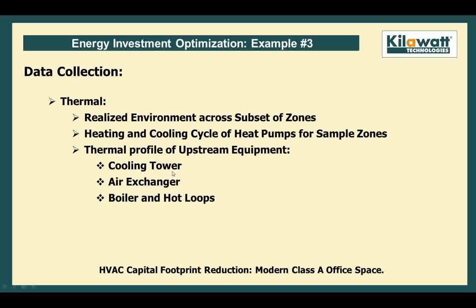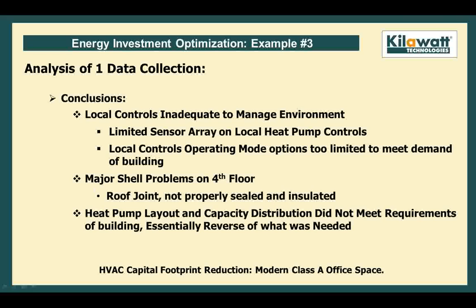The conclusions of our first level of data was that there was basically very little control, a very limited sensor array. There were no operating control sequences at all. In addition, we also found, once again, a major shell issue on the fourth floor. In the construction of this building, it was all built at the same time, but the first 3 floors were occupied, and the fourth floor was left vacant for a period of time until the tenant moved in. The tenant was in charge of finishing his fourth floor, and unfortunately, whoever finished it for him forgot to insulate the roof.